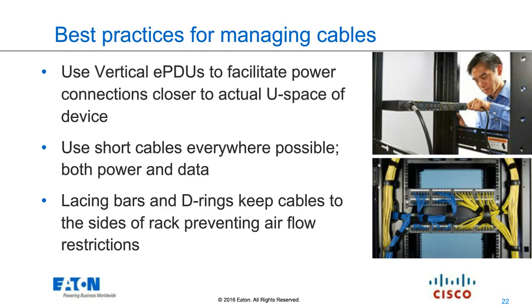When it comes time to build out the white space, converged infrastructure boxes are great because they show up ready to be installed, but that's a small piece of the market, so the rest must also be accounted for. Managing cables is very important here — rack hygiene, as we usually call it — because airflow through the rack, front to back, is what differentiates a successful deployment that doesn't overheat from one that tends to overheat and cause failures.